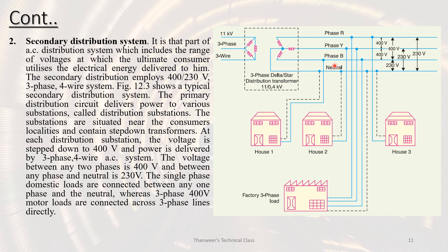In secondary distribution, a 3-phase 4-wire system is used. The 4th line is the neutral point. The phases are R, Y, and B. For 3-phase loads, the line-to-line voltage is 400 volts. For single-phase loads, the line-to-neutral voltage is 230 volts. This is the secondary distribution system used to supply both 3-phase and single-phase consumers.